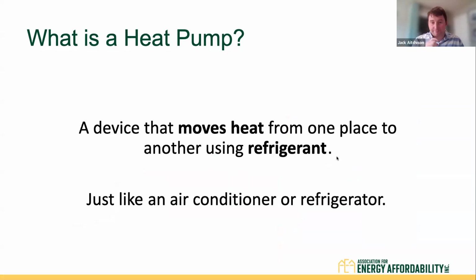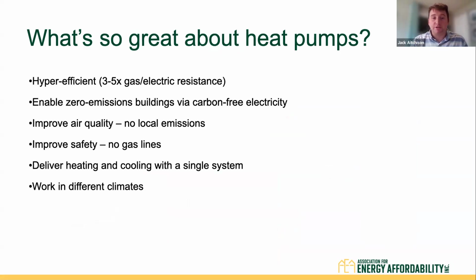Next slide, please. So in layman's terms, a heat pump is a device that moves heat from one place to another using a refrigerant, just like an air conditioner or refrigerator. Next slide, please. So what is so great about heat pumps and why are they so important for the electrification movement? Well, they're hyper efficient, and that's really the key here. Because they're moving heat, not generating heat, they are 3 to 5 times more efficient than gas or electric resistance. If you compare the cost of 1 BTU of gas versus 1 BTU of electricity, gas is going to be cheaper. But if you consider the efficiency, if heat pumps are 500% efficient, they're going to draw less energy to create the same amount of heat. And so that's where you counteract that difference in costs.